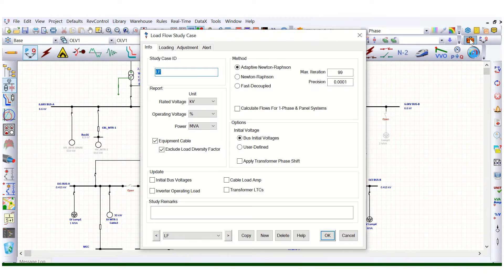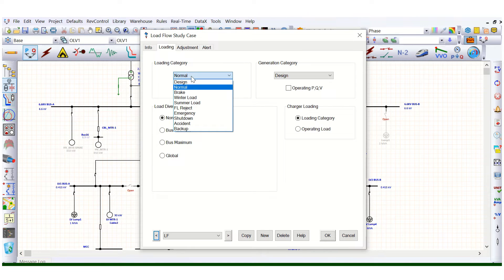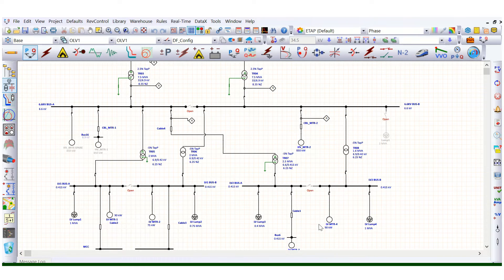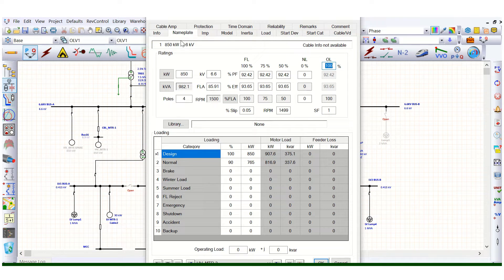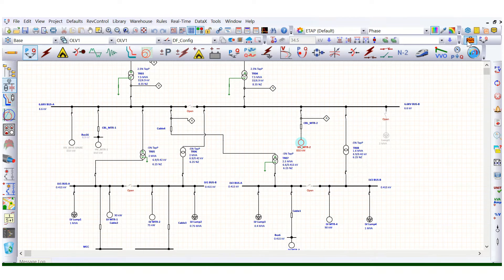If we check here under this load flow study case editor, we can see the loading. The load diversity factor is not assigned, but the loading category is selected as normal. Normal means, for this motor, under the nameplate tab, normal means 90 percent of the connected load. If we select the design load, that means it will take 100 percent, that means 850 kilowatt. If we select normal load, that means 90 percent of 850 kilowatt.